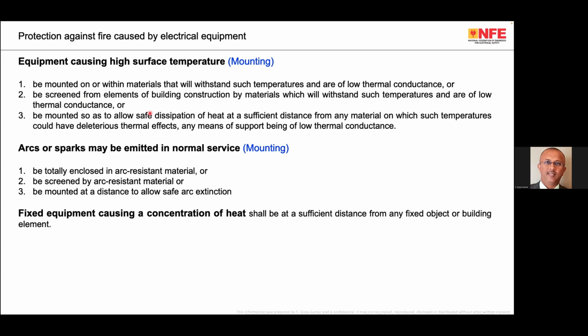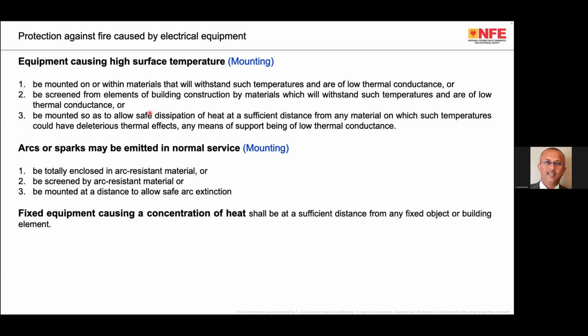Some equipment produces arcs or sparks during operation. It is an inherent property that when it starts, there may be arcing. Such products have to be put inside arc resistant material, or screened by arc resistant material, or mounted at a distance to allow safe arc extinction. You will be able to get this data from the manufacturer's catalog.